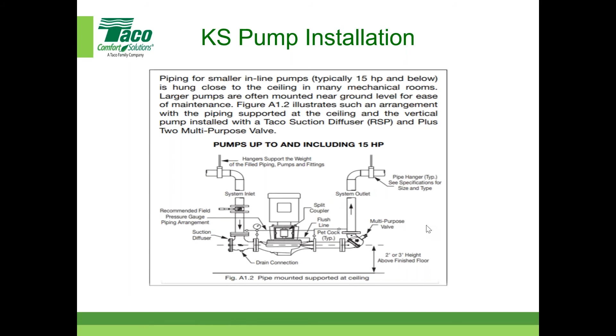You can see some of the different piping arrangements here. Larger pumps, larger than 15 horsepower, need to be supported on isolation pads, and you always want to make sure it's done correctly. Hangers support the weight of the filled piping, pumps, and fittings. Very, very important.